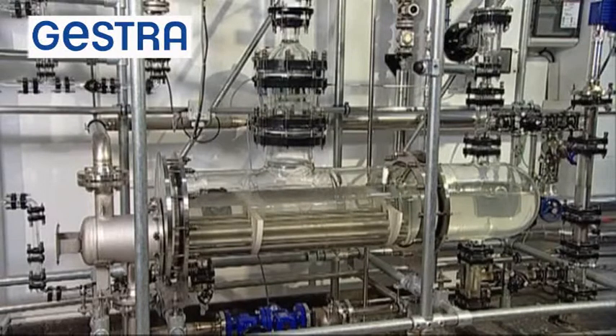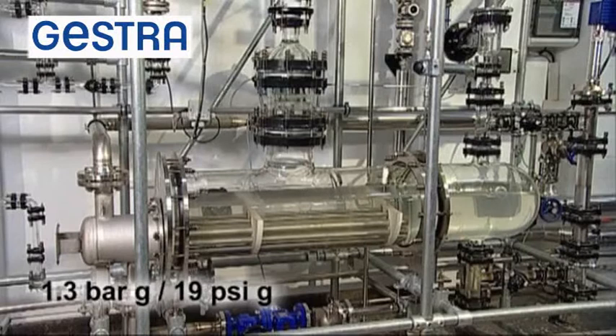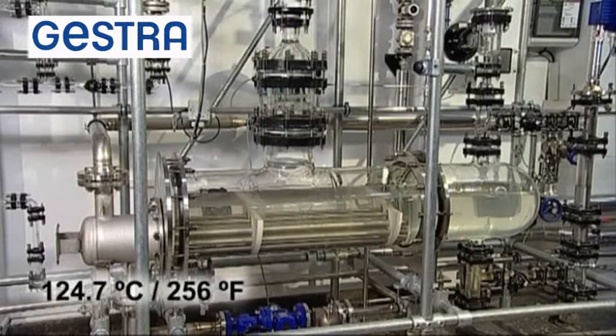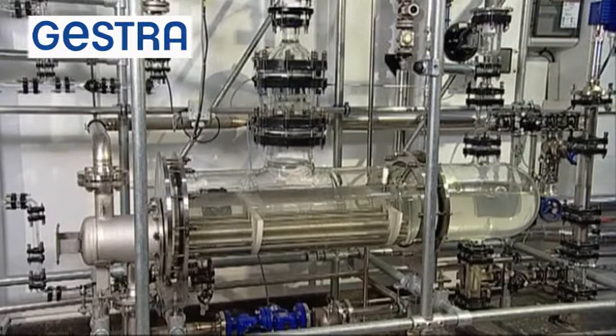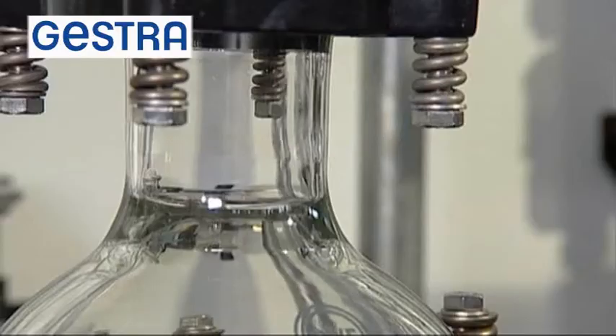The steam generator is now filled with saturated steam at a pressure of 1.3 bar gauge and a temperature of 124.7 degrees centigrade. This temperature must be identical to the water temperature, otherwise no saturated steam could have been formed, and moreover, two media with different temperatures in the same vessel can lead to thermal shocks. Saturated steam is invisible. Only when it enters the atmosphere do the first steam bubbles immediately condense to form minute water droplets, which are then visible. However, this type of steam is then known as wet steam because of the water droplets it contains.